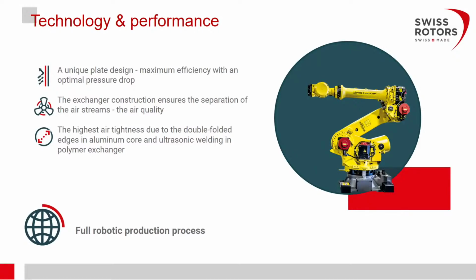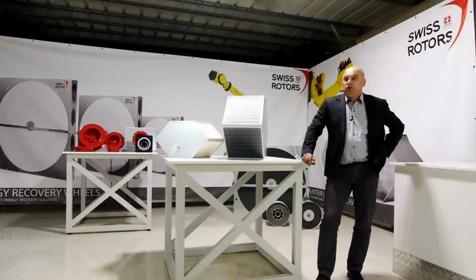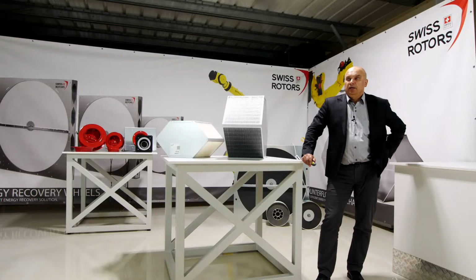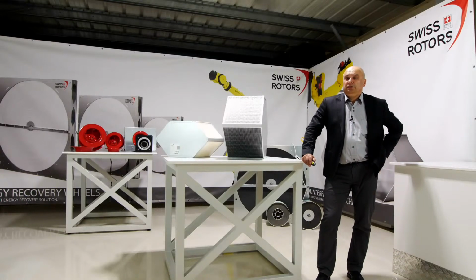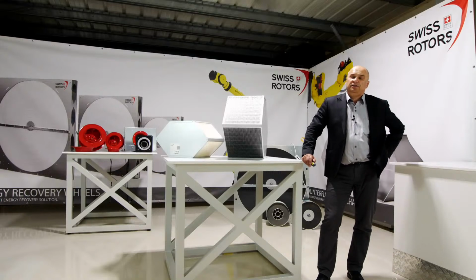But there could also be a polymer core, which is much easier to fold, and then we can reach a higher exchange surface and, of course, increase the distance between the plates. That means we can have a lower pressure drop with high efficiency. So this allows for these high impact polystyrene core plates.